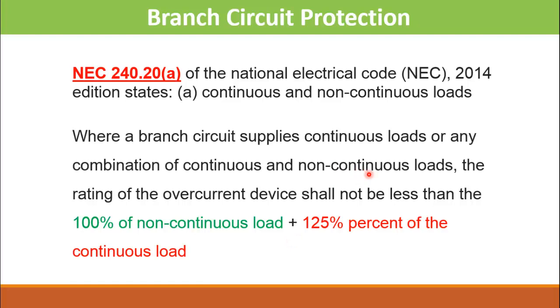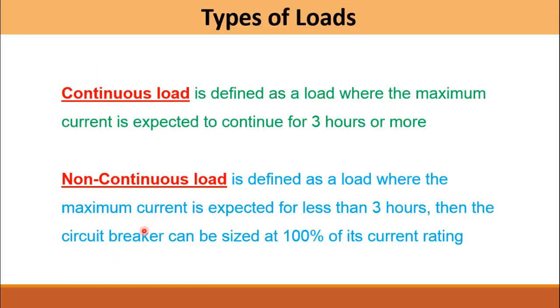NEC classifies the load into two types: continuous load and non-continuous load. In most videos and literature, the circuit breaker is sized at 125% of the total load. However, NEC states that for continuous loads the circuit breaker must be sized at 125%, whereas for non-continuous loads the circuit breaker can be sized at 100% of the total full load current.